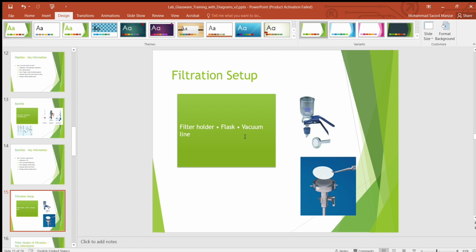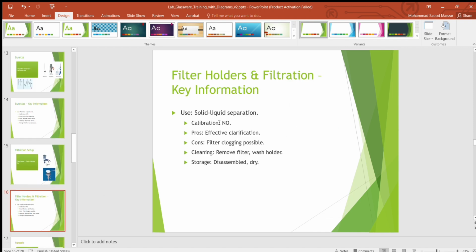These are the filtration setup: filter holder, flask, vacuum line, and these are also a different kind of filter holder. These are also filter holders. You have seen this in my previous videos where I was talking about vacuum filtration or dead-end filtration. And it doesn't need calibration. Effective clarification. Cleaning: filter clogging is possible if a lot of solids pass through the filter, which may or may not be retained on the filter. So it needs thorough cleaning. Remove the filter, wash the holder, then reassemble and clean them separately.